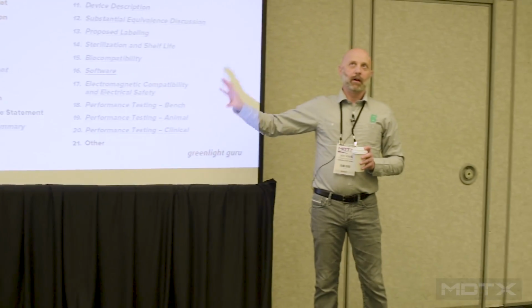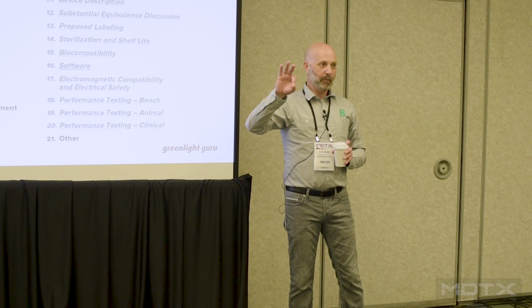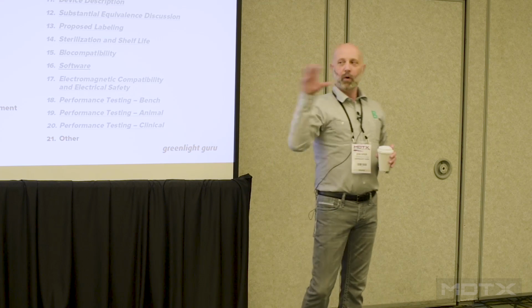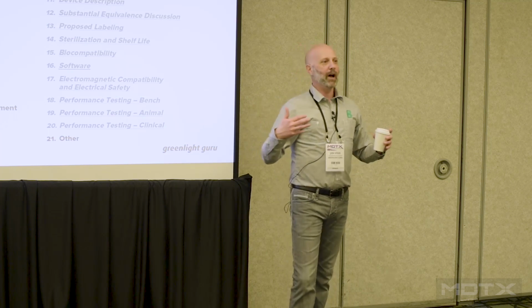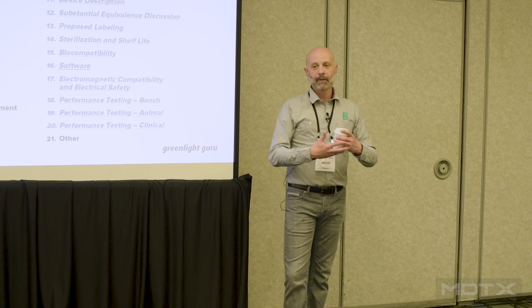The other thing that I would add is determining your 3-letter product code. Generally speaking, not always, that will give you some level of information about whether or not there is a guidance document that relates to your product, whether or not there are consensus standards that relate to it, and help you identify, as Juan Carlos said, possible predicates that relate to your product.